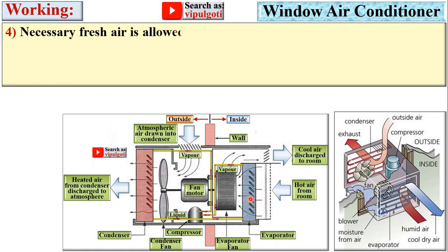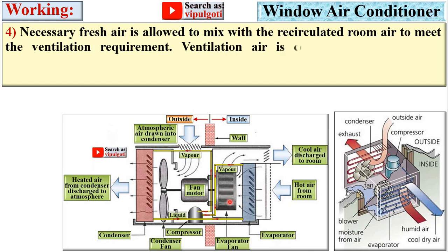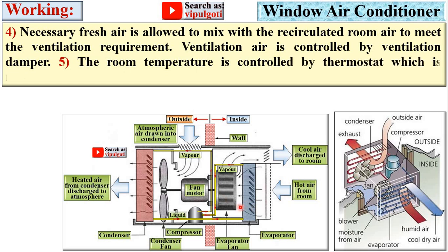Next, necessary fresh air is allowed to mix with the recirculated air to meet the ventilation requirement. And ventilation air is controlled by ventilation damper. The room temperature is controlled by thermostat which is required to turn on and off power supply to the compressor motor.